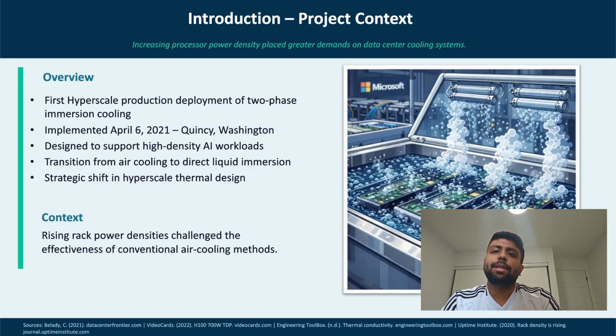The system works by submerging servers directly into dielectric liquid. This liquid has a boiling point of approximately 50 degrees Celsius, or 122 degrees Fahrenheit. As a server operates and generates heat, the liquid absorbs the heat and begins to boil. The vapor rises, makes contact with the condenser, cools down, and returns back to liquid in a closed loop cycle.